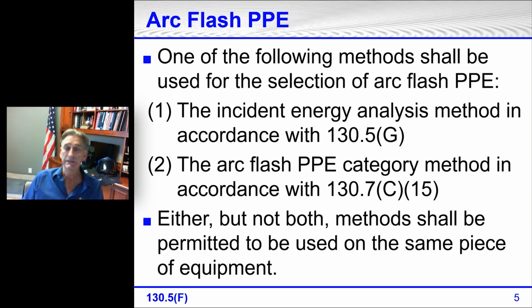That's when a company or facility either does it in-house or has someone come in and do an arc flash analysis, and they'll put labels on equipment. You can look in 70E to find out which equipment is required. It's equipment that's likely to require examination, adjustment, servicing, or maintenance while energized. It doesn't apply to dwellings. If a facility has labels, then electricians, maintenance personnel, and technicians will look at the label to determine what arc rated PPE they need to wear.